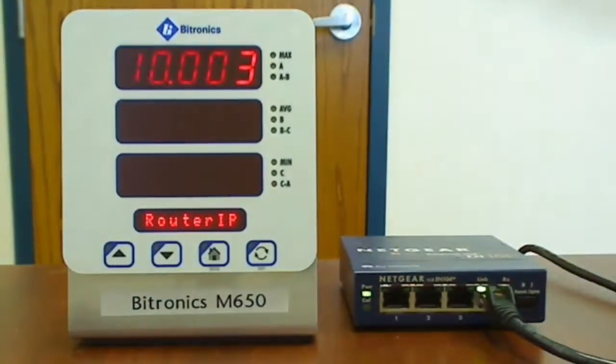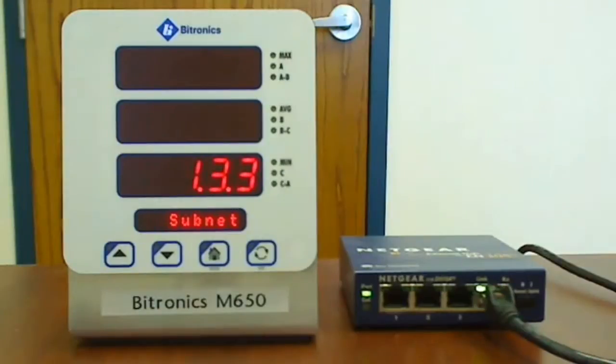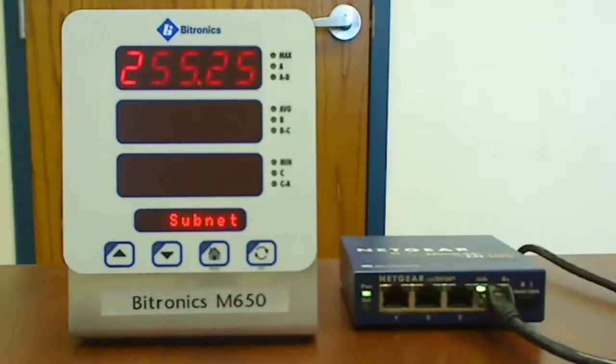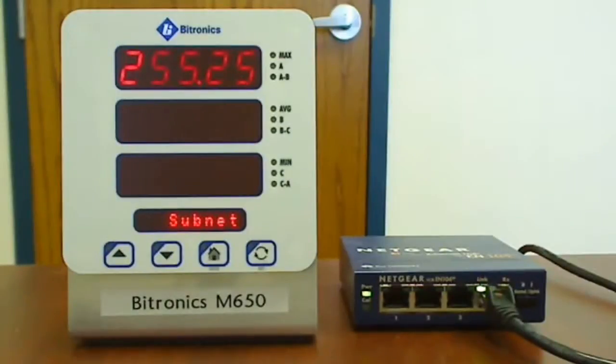Hit the exit key to escape back to the settings index. Hit the down arrow key once to advance to the subnet mask. Hit the enter key to enter this section. We've been asked to mask this meter for a class C network, so that's 255.255.255.0.